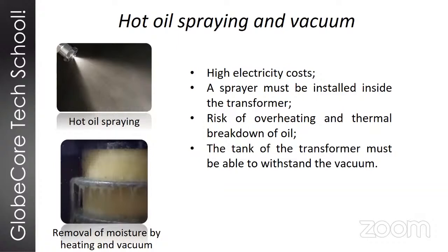Next one we're going to look at is circulation and spraying of hot oil in vacuum. This is used both in repair shops and in the field to dry transformers of small, medium, and large size. To perform this process, you'd need an oil processing rig, an oil processing machine that includes a heater and a powerful vacuum system. And you also need special nozzles for spraying the oil. So the oil purification system is connected to the transformer. It creates a closed circuit through which the oil circulates continuously. So hot oil circulates through the transformer in parallel for more even heating of the windings.